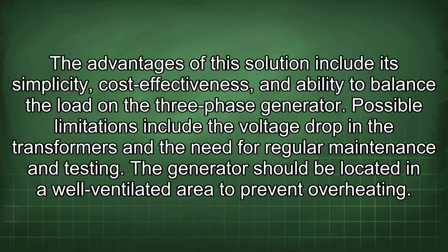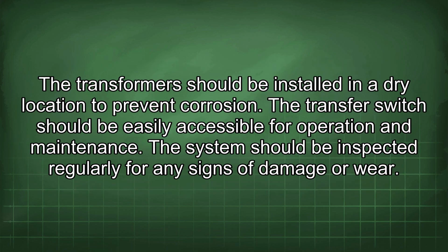The advantages of this solution include its simplicity, cost-effectiveness, and ability to balance the load on the three-phase generator. Possible limitations include the voltage drop in the transformers and the need for regular maintenance and testing. The generator should be located in a well-ventilated area to prevent overheating. The transformers should be installed in a dry location to prevent corrosion.